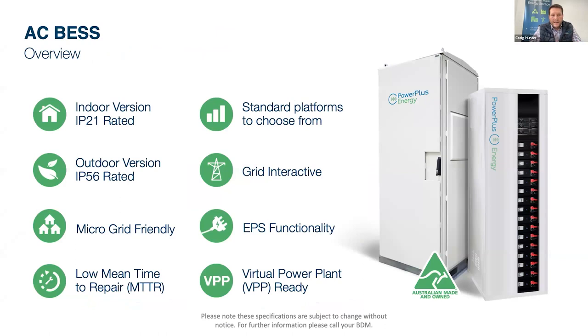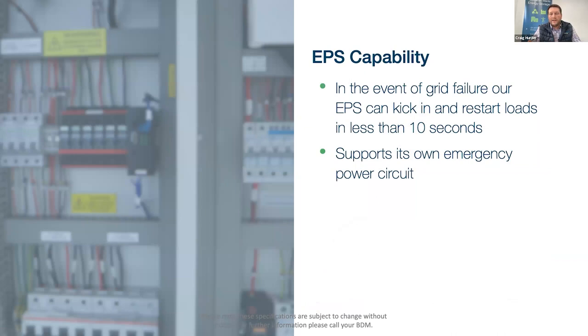One of the key differences to this product is it's only a grid interactive product, not for off-grid applications. It doesn't have UPS functionality, it has EPS functionality in the back end. So what is EPS functionality? Essentially, the system will shut down in the event of a blackout, but then will power back up after 10 seconds and power your essential loads. No solar can remain connected during this process, but it's definitely going to give you an extended blackout. With the Escape 20, the solar can remain connected, giving you the extended blackout and the true off-grid capabilities.